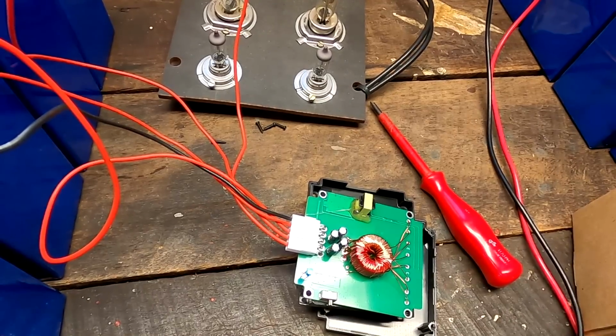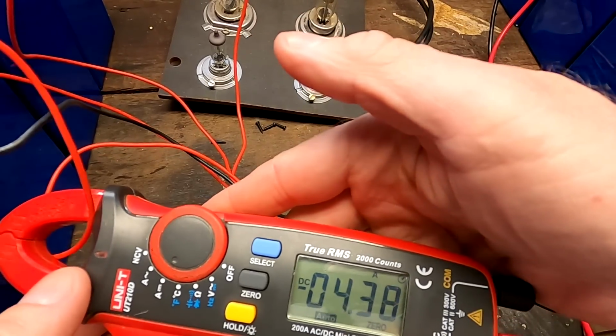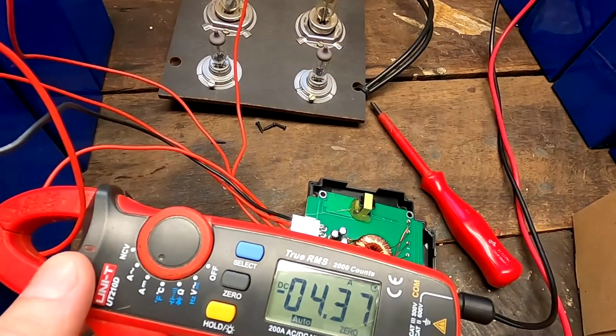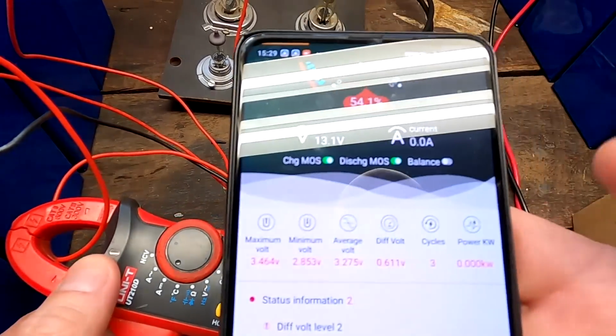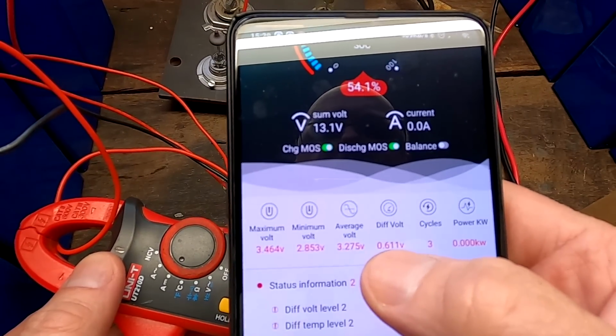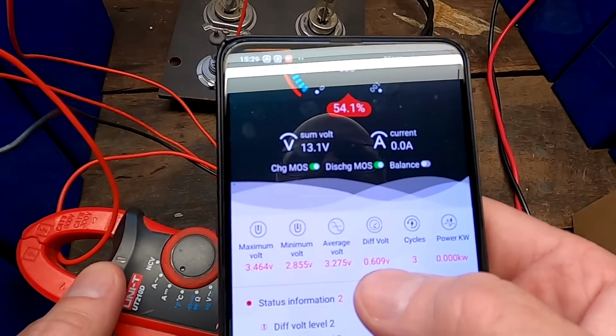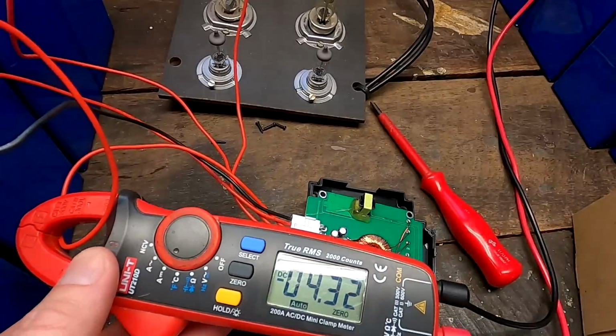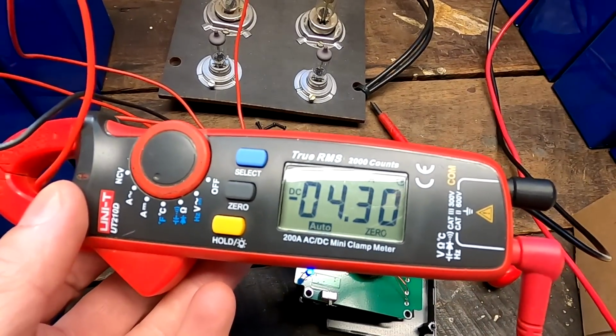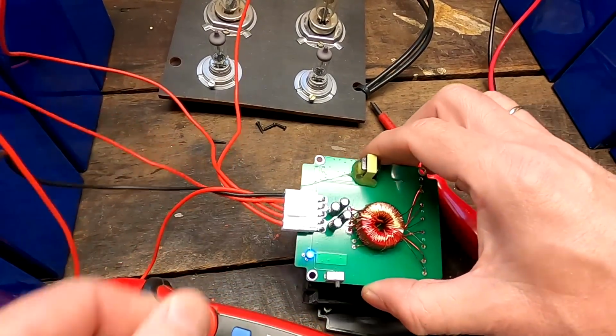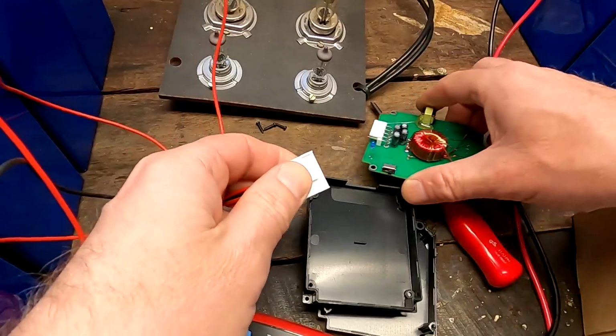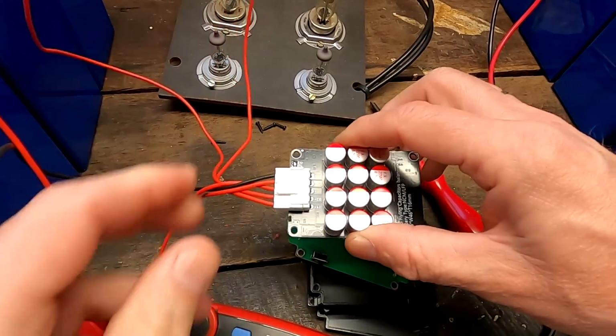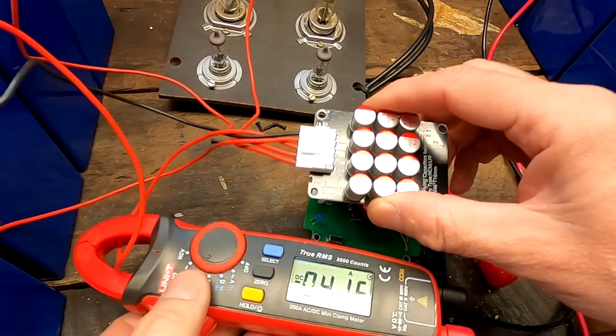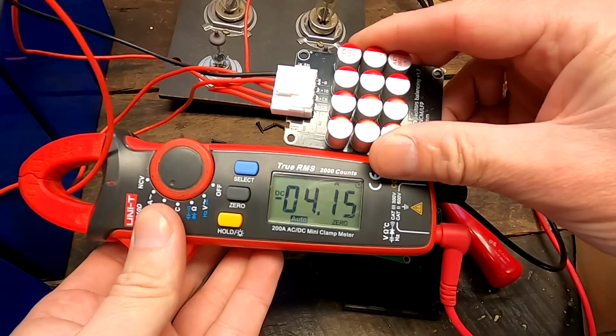Light comes on, 4.3 amps, even though we have 611 millivolt deviation. There you can see it, 600 millivolt deviation. This should give us at least 9 amp of balance current. But here we go, 4.3 only. Let's try the other one again. Yeah, 4.15.